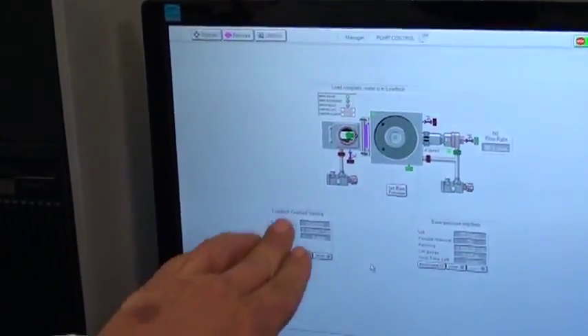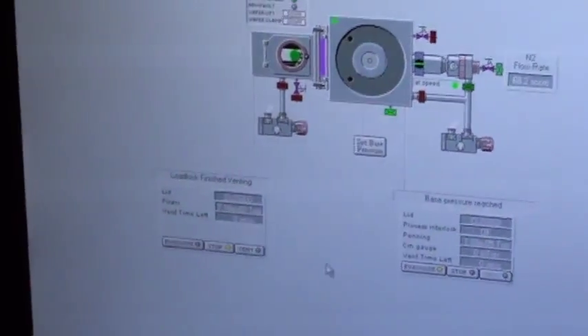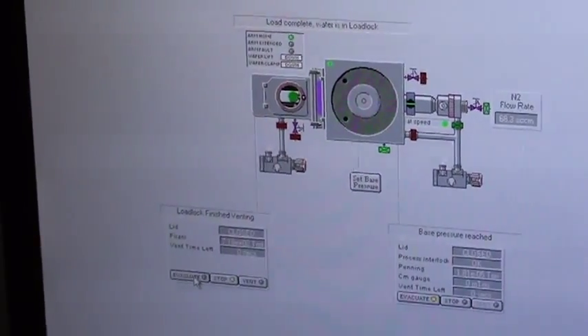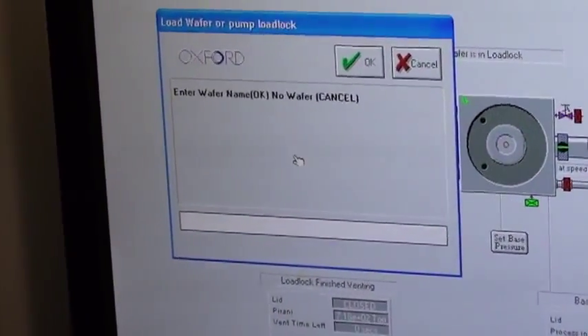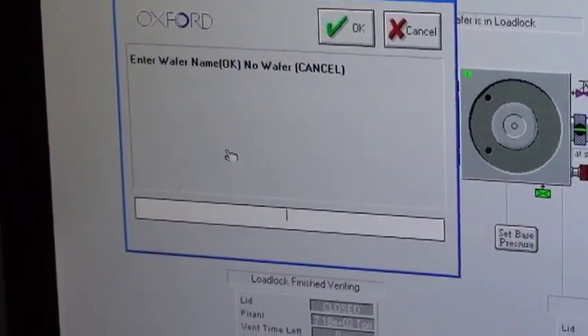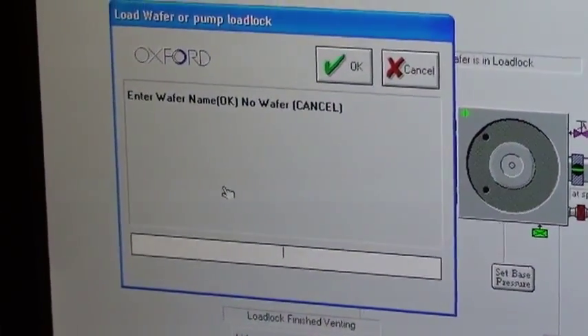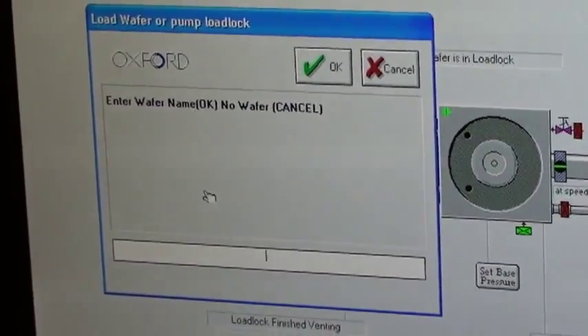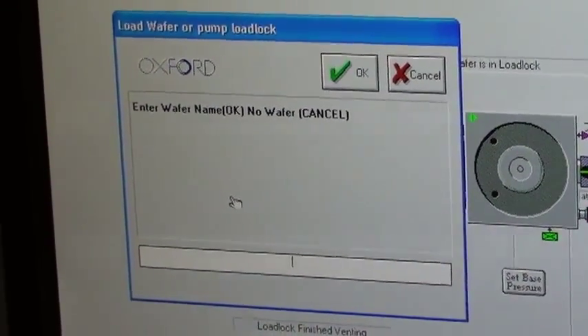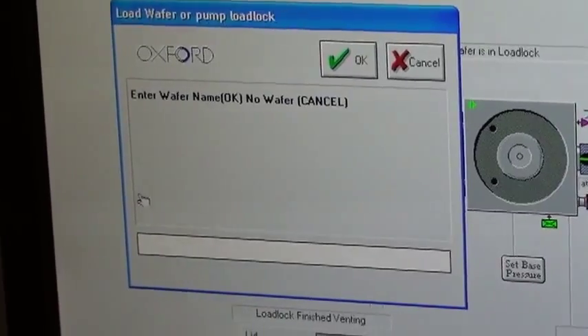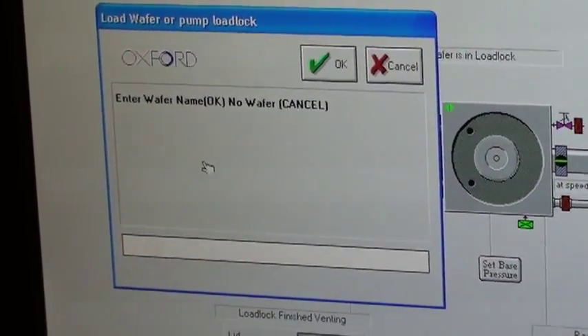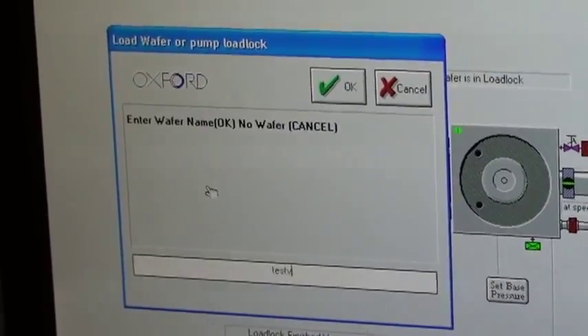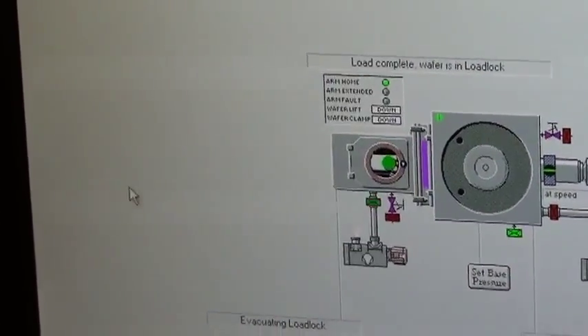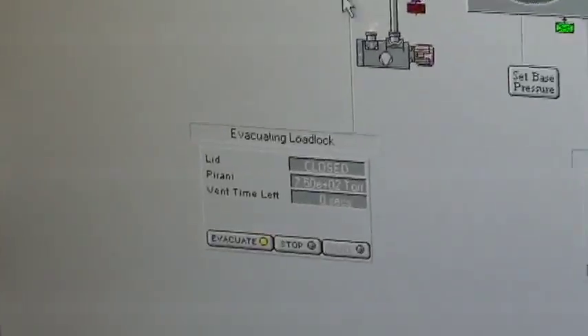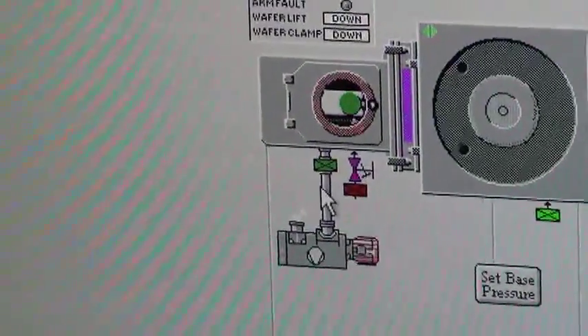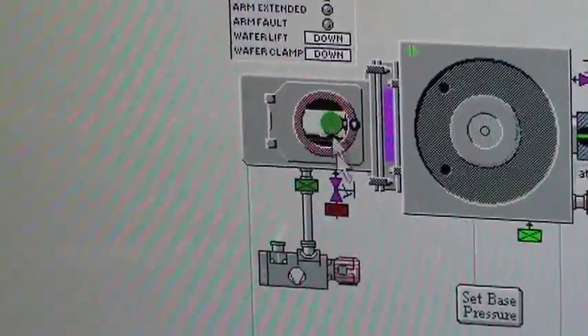This is load lock control. This is chamber control for vacuum only. So I'll tell it evacuate. You will call the wafer. It says you want to name your wafer. You can put lot numbers, serial numbers, however you wish to track your wafers. And this gets data logged in the system so you can pull up the charts after the run and check all your parameters. Alright, so it opens the rough valve to the chamber. This shows wafer in chamber.